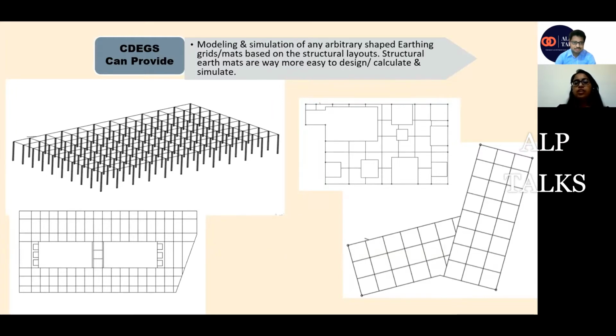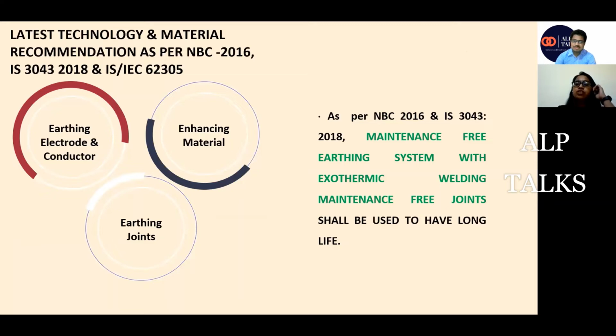Because for underground work, it happens that I get a foundation of a column or pillar, so I need to skip that space, and I have to lay my earthing in the remaining space. That was not possible with AutoCAD designing or with the Excel sheet. I cannot consider those footings of columns in my calculation with Excel sheets. But now with this software, I can do that, and I can validate the design also. So this is the advantage of moving to the software from the Excel sheet.